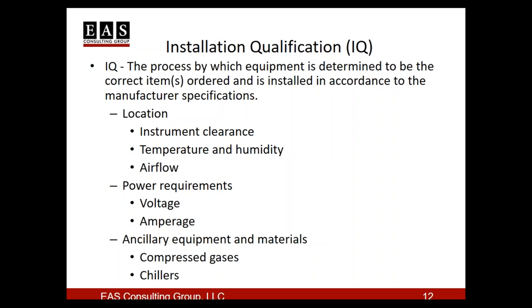This is the IQ portion - the process of installing the equipment. You have to pick the location and make sure the instrument has appropriate clearance. Even something simple like a refrigerator has to have 4-inch clearance in the back, depending on the model. You have to have temperature and humidity control in the laboratory to make sure the instrument can operate in those conditions.